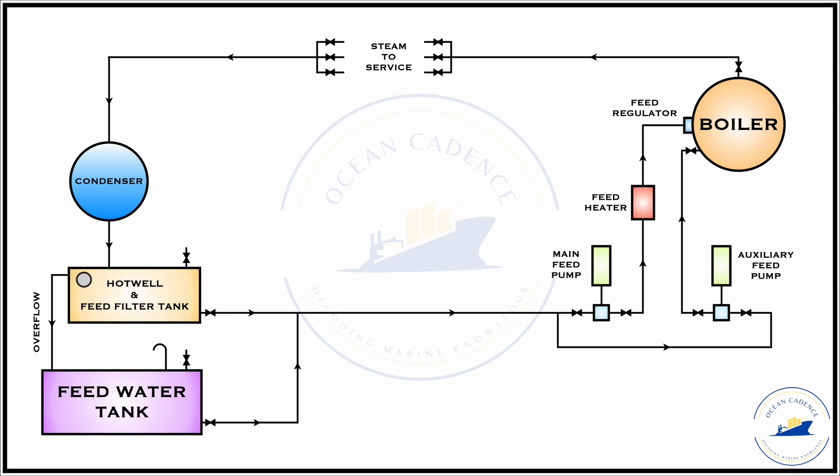That is why it is usually prescribed that the hot well has to be kept at a temperature at least over 80 degrees and ideally near to 84 to 85 degrees. It has just to be made sure that steaming does not heavily start within the hot well itself. Also in some ships you will have an intermediate dosing unit after the hot well and then thereafter the dosed water with a regulated pump that is a regulator unit and a small piston pump assembly. It will be dosing continuously into the feed water line when the circulation starts and stops, or in some ships you can directly batch dose the chemical into the hot well itself. Again this is very individually dependent upon the design of the vessel.